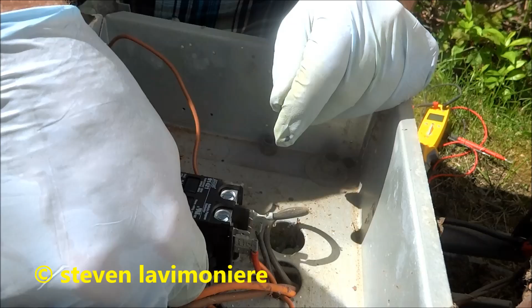Now I had got footage on checking all the controls and everything upstairs, but my camera dropped and I lost it, so you're gonna take my word for it. So this 24 volt coil on here shorted to ground basically, and then that fried. You can tell it's all cooked anyway. And that fried the transformer upstairs. That's what the problem was.